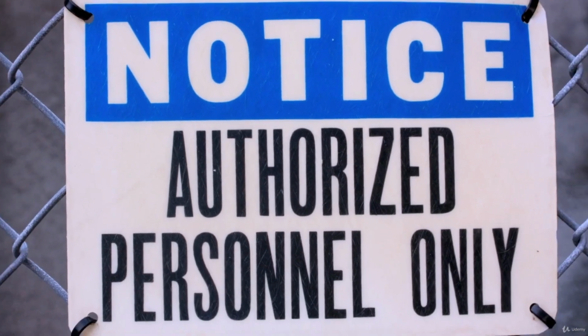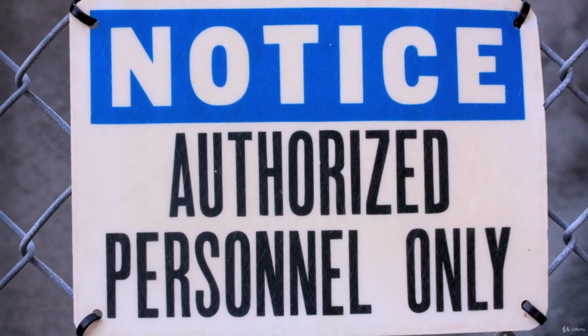In addition, live parts of electrical equipment operating at 50 volts or more must be properly guarded against accidental contact. This is achieved through approved cabinets or enclosures, location, or permanent partitions so they are accessible only to qualified persons or through elevation of 8 feet or more above the floor or working surface. Guarded locations must be marked with conspicuous warning signs. If there is a chance that the live parts of electrical equipment can be exposed to physical damage, they must be enclosed or guarded.